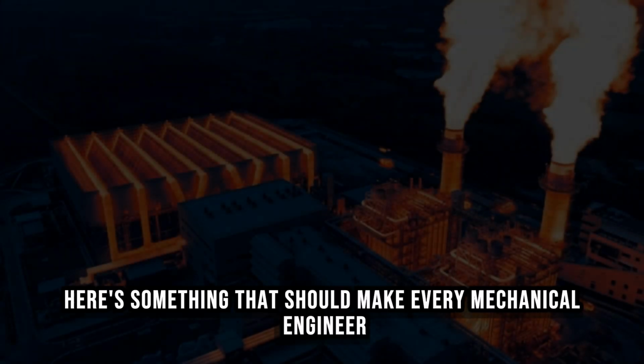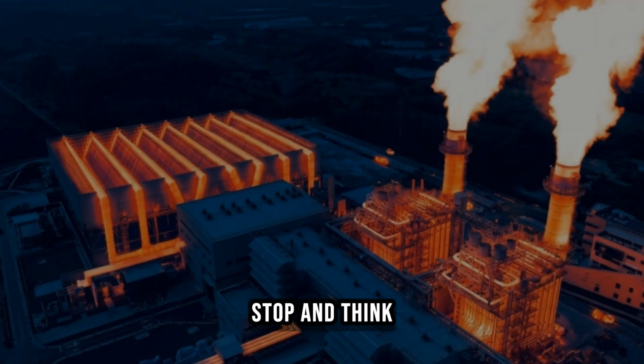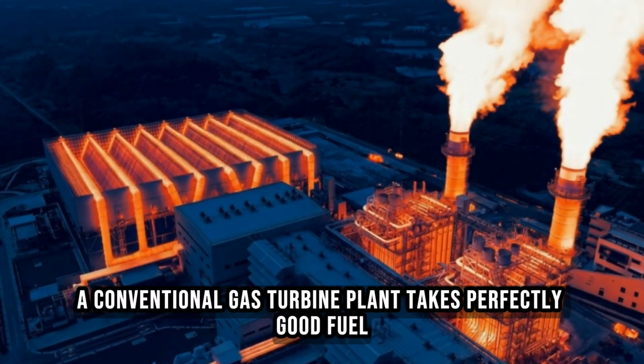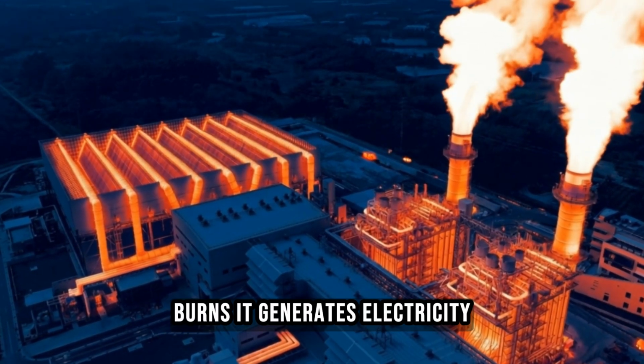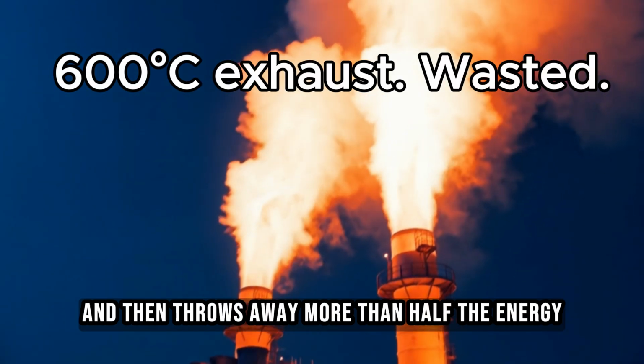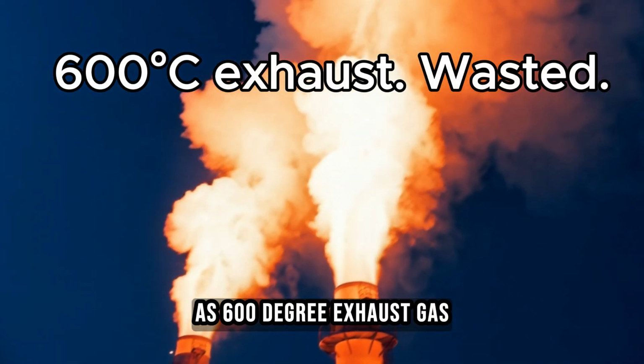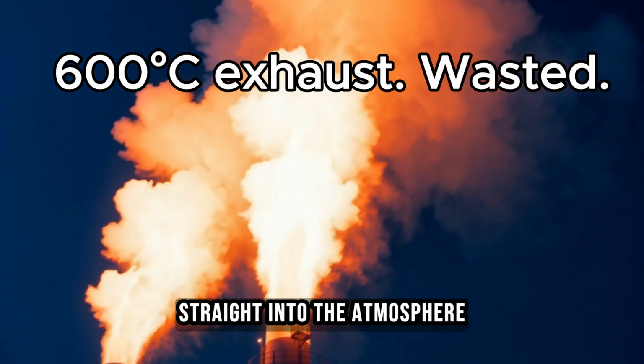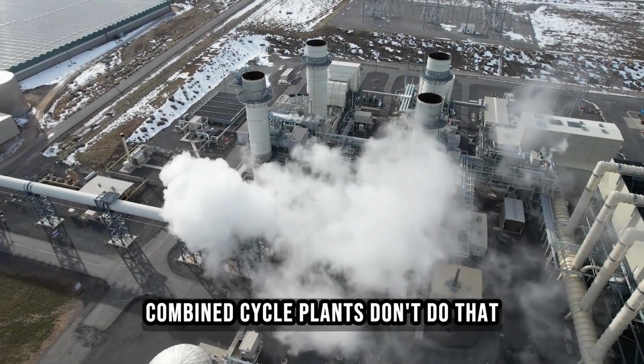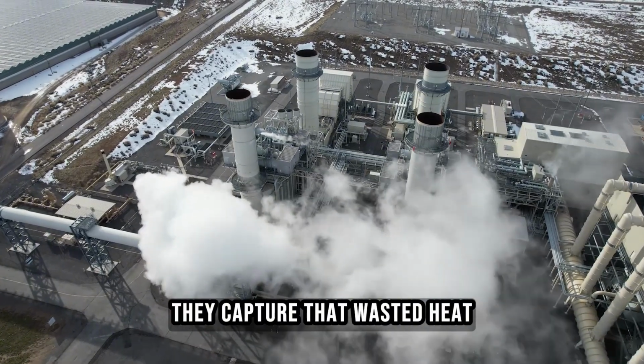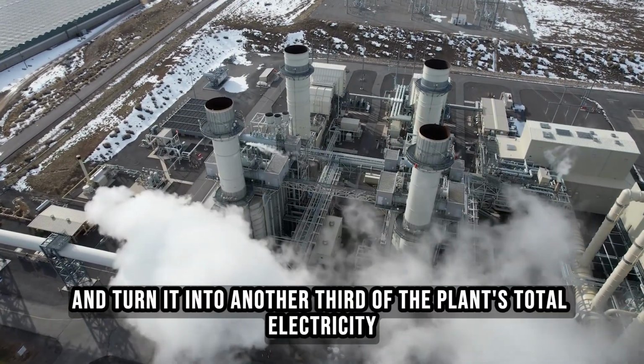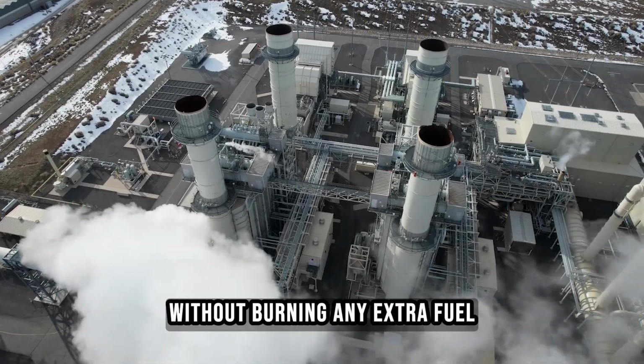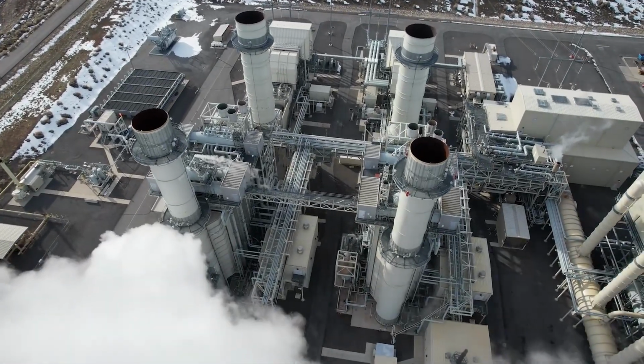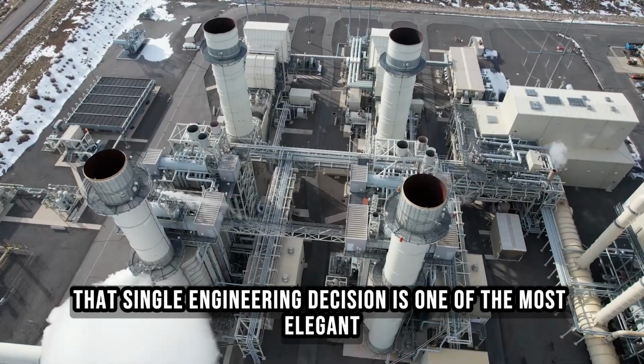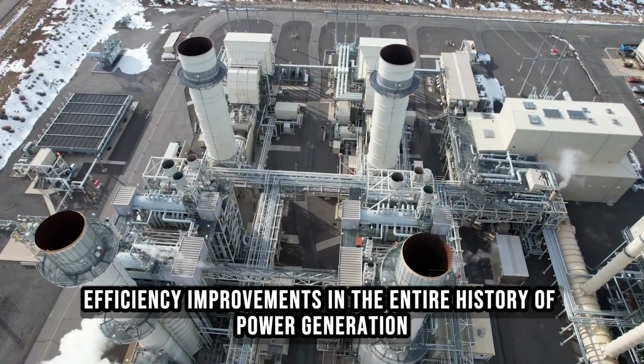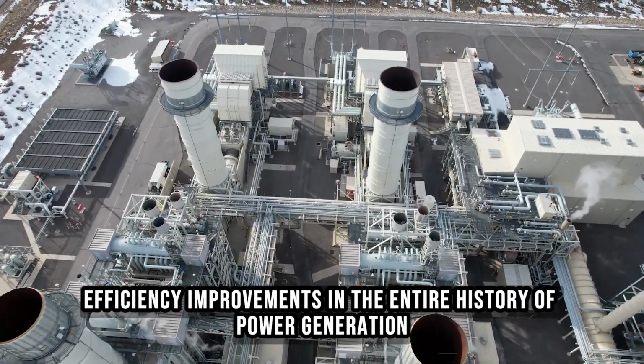Here's something that should make every mechanical engineer stop and think. A conventional gas turbine plant takes perfectly good fuel, burns it, generates electricity, and then throws away more than half the energy as 600-degree exhaust gas straight into the atmosphere. Combined cycle plants don't do that. They capture that wasted heat and turn it into another third of the plant's total electricity without burning any extra fuel. That single engineering decision is one of the most elegant efficiency improvements in the entire history of power generation.